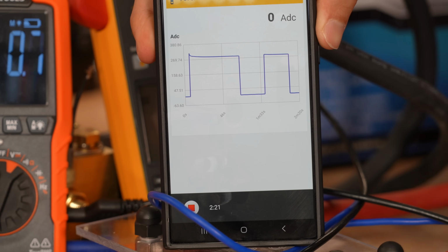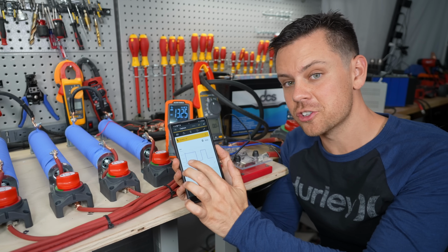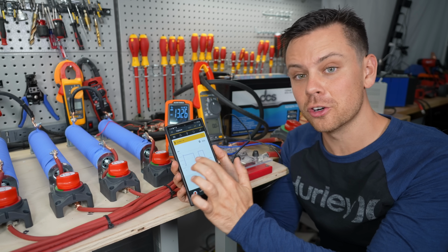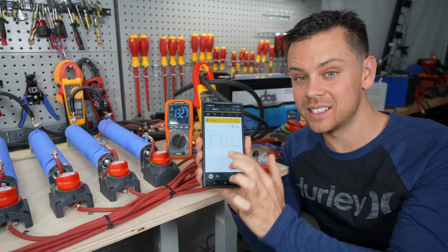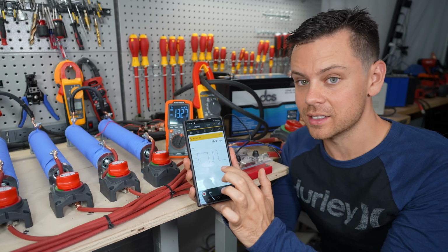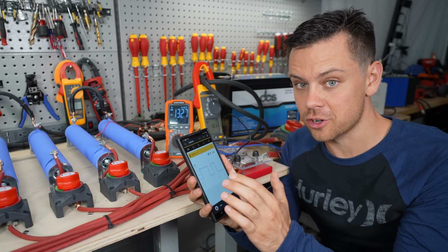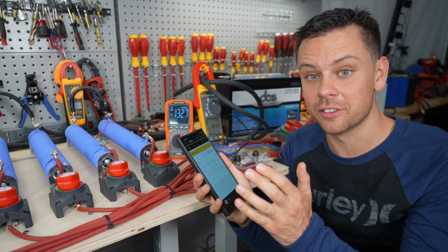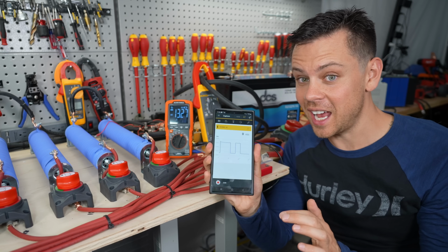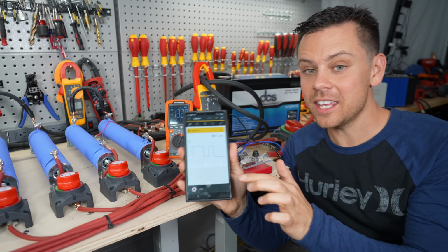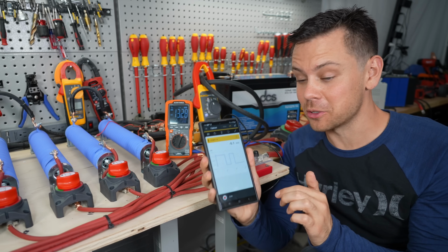So let's turn it off. We hit 300 amps and then it dropped. The first draw lasted a whole minute, but the second draw lasted only 20 seconds. So let's crank it over 300 amps and see if it will disconnect in under 5 seconds. But that was a good test, it did really well for that, and the overcurrent protection did trip, so that's awesome.